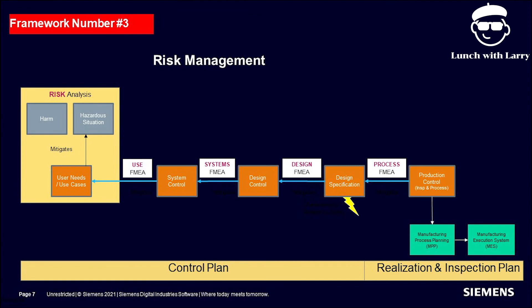Now, the last thing I'm going to talk about here is really associated with the systems modeling. And in systems modeling, we really have three different types of data that we want to be concerned with. So the first one is the set of design controls. Now, these design controls are requirements, and they're a flat view of what we need to do the testing. So as we enhance this model, the idea is when we're done with developing these controls, we'll execute our test management system, and not only will it say, did we meet our set of controls, but also it will assure that we've mitigated all the hazardous situations that we've identified in our risk management system. So the testing serves a dual purpose.